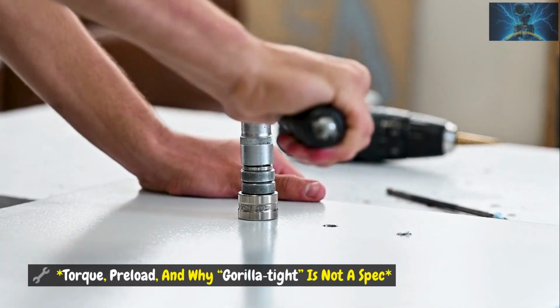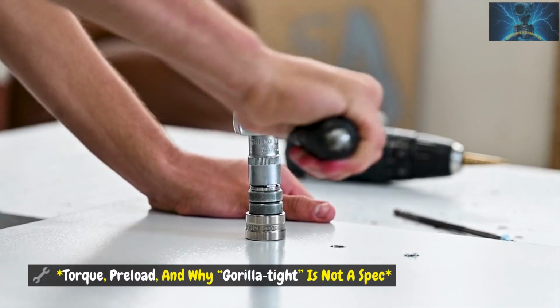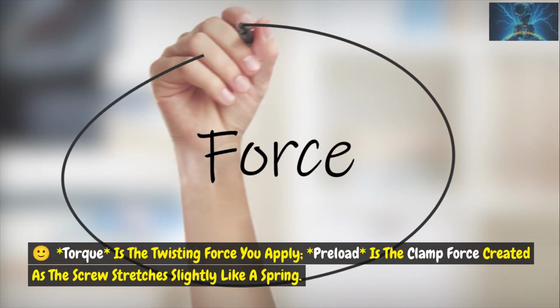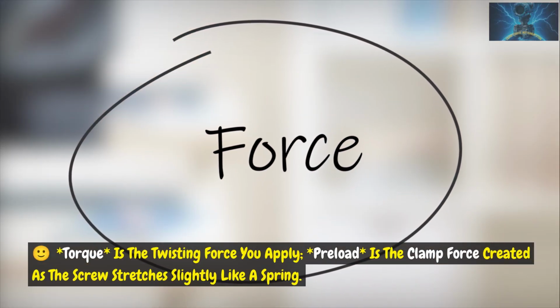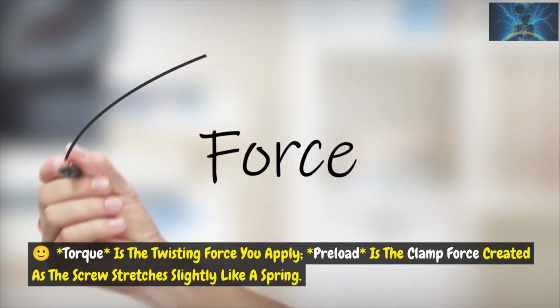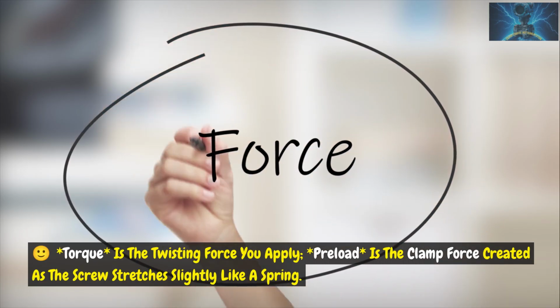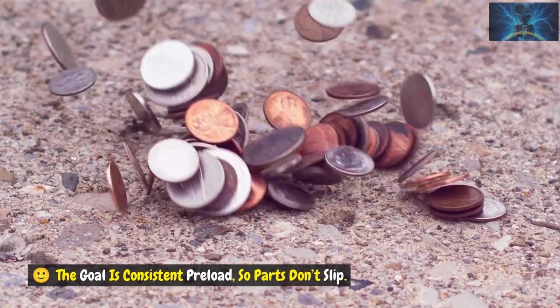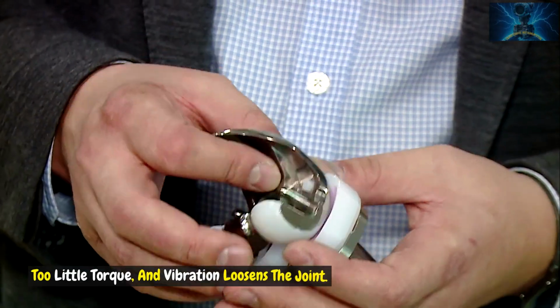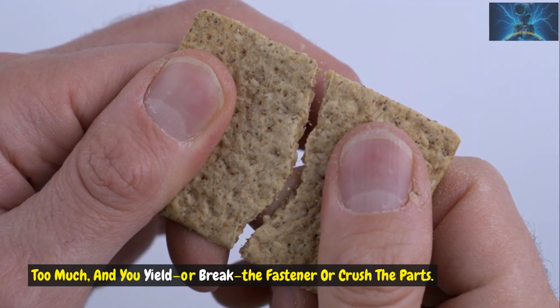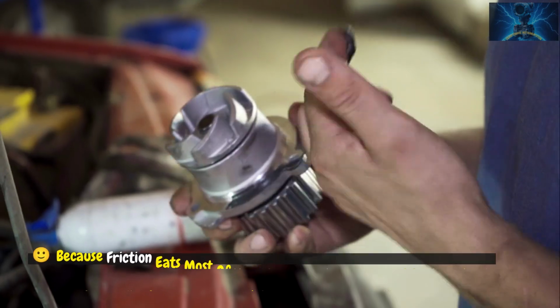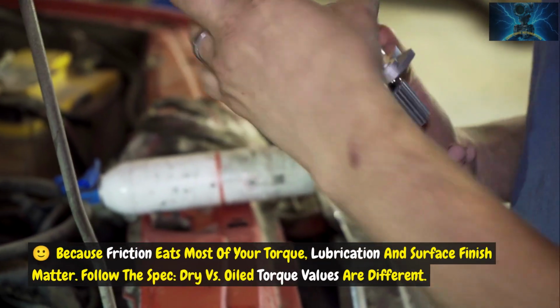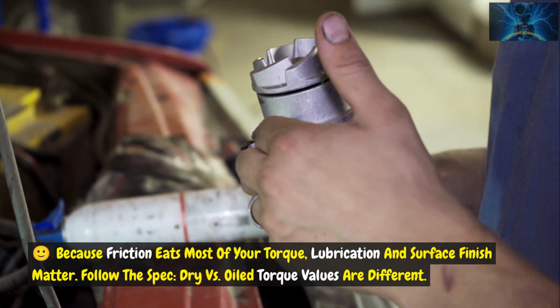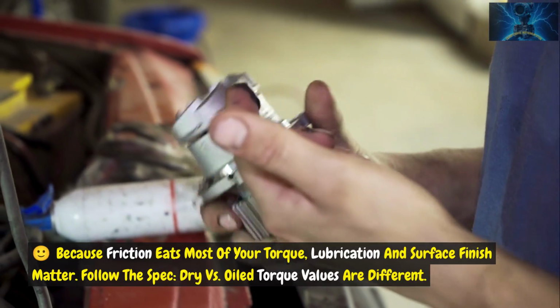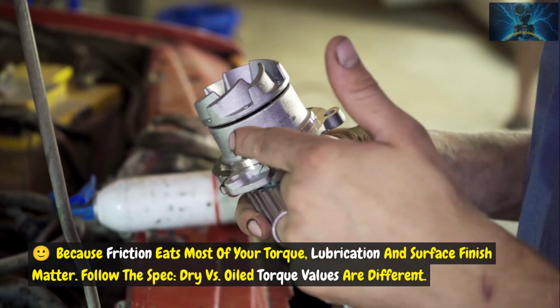Torque, preload, and why "gorilla tight" is not a spec. Torque is the twisting force you apply. Preload is the clamp force created as the screw stretches slightly like a spring. The goal is consistent preload so parts don't slip. Too little torque and vibration loosens the joint. Too much and you yield or break the fastener or crush the parts. Because friction eats most of your torque, lubrication and surface finish matter. Follow the spec. Dry versus oiled torque values are different.